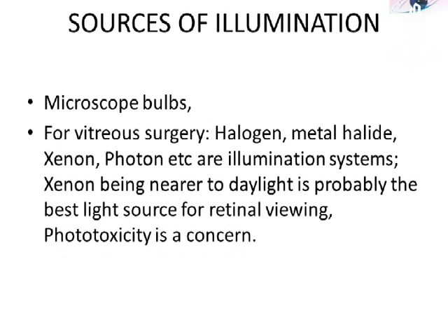The source of illumination for video shooting in the posterior segment is microscope bulbs, halogen, metal halide, xenon, photon, etc., or other illumination systems. Xenon being nearer to daylight is probably the best light source for retinal viewing. You must always be careful about phototoxicity.